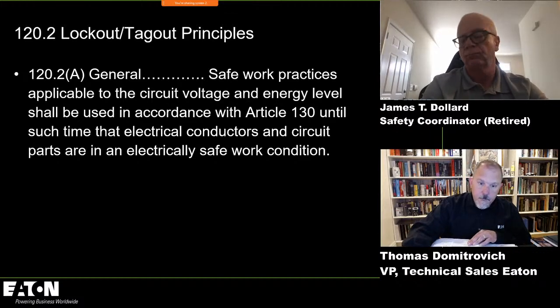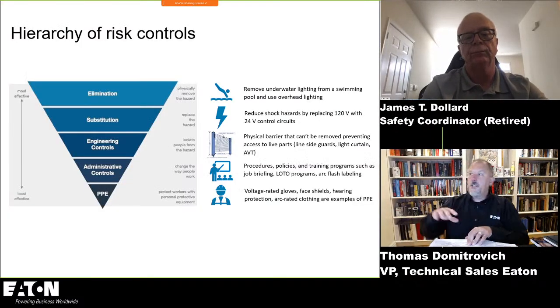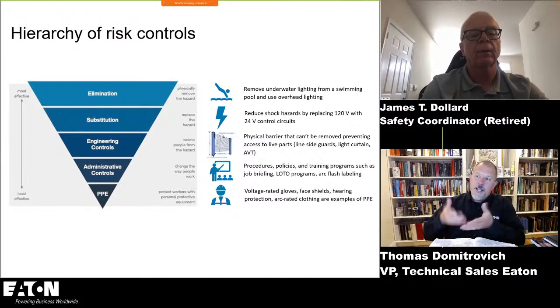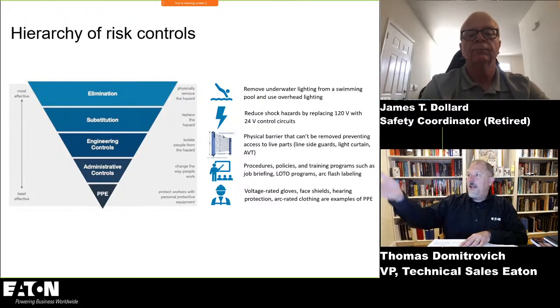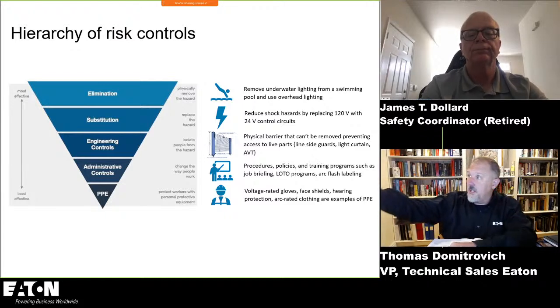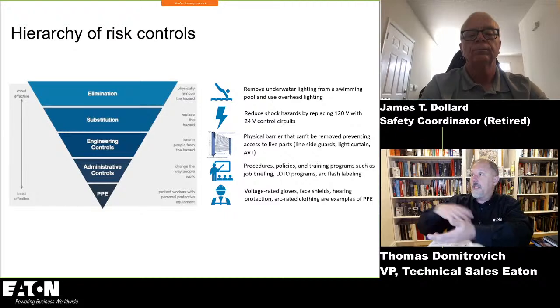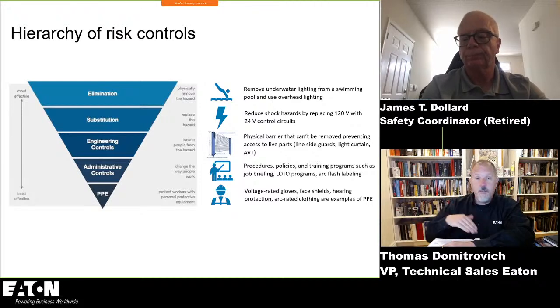Gotcha. And this one here just shows that hierarchy. Everybody shows it as a triangle, and shows that PPE is your last resort. And this gives, like you gave one of the examples, for replacement or substitution. Replace 120 volt circuits with 24 volt control, because 50 volts is that limit. Anything at 50 and below, you don't have a shock hazard associated because you don't have enough voltage, right?